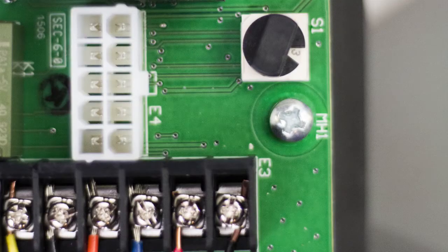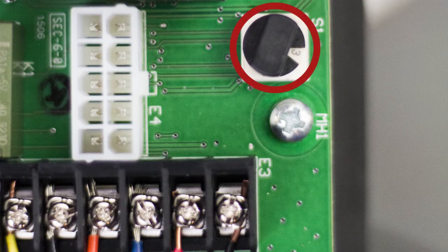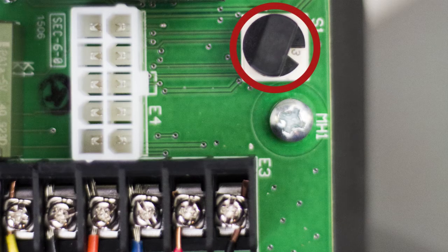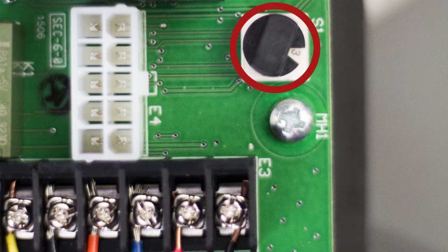There is a rotary switch on the lower right corner of the circuit board. This is used to set the retard time. The settings are in 10 second increments from 0 to 90 seconds.